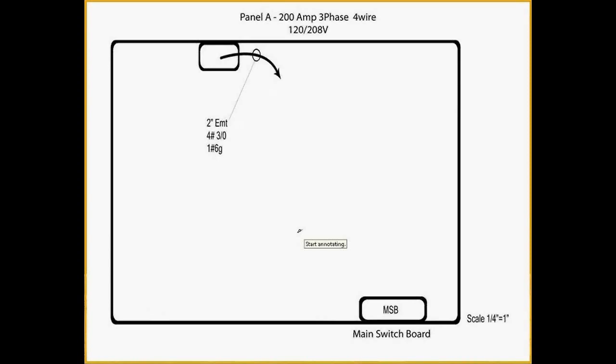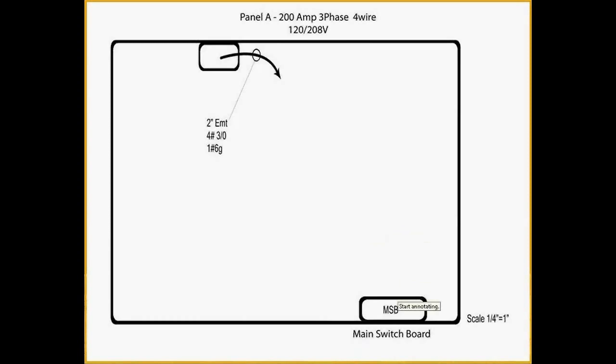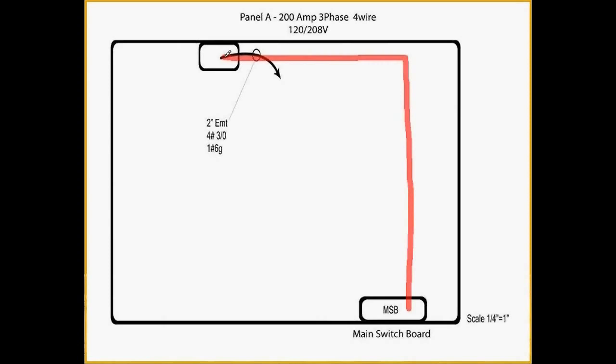And here's a tip for taking off conduit. Take off all conduits at right angles to the plant. Do not measure on diagonals. By measuring at right angles, you allow enough conduit and wire to go around obstacles in the building. Just like this. You roll it off at right angles to the building.